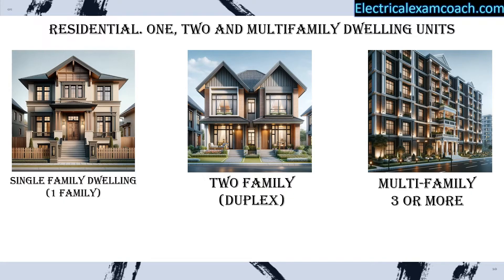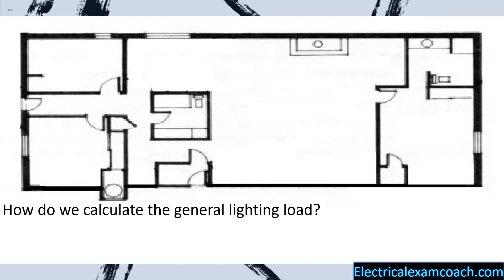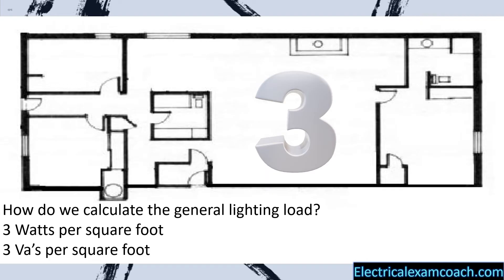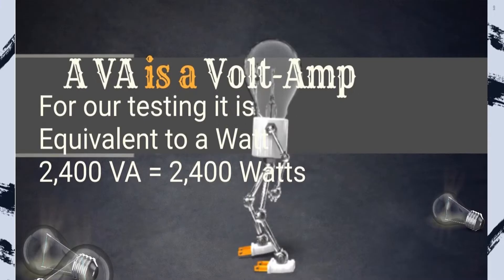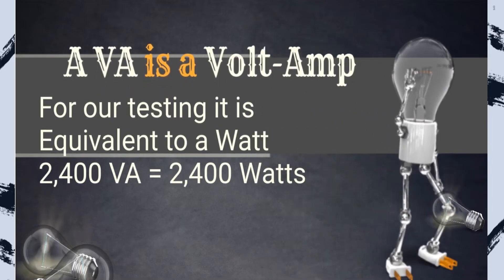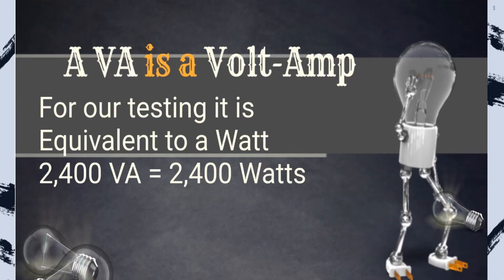The first question we have to ask is how do we calculate the general lighting load? Are we going to calculate it per receptacle outlet, per lighting fixture — do we have to count them all up? Thankfully, no — they've made it very simple. We're going to calculate it at three watts per square foot. So for all of the general lighting and all of the general receptacles, all we have to do is take the square footage of the dwelling unit and multiply it by three. The code language actually uses VAs — volt amps — so three VAs per square foot. For our testing, a VA is equivalent to a watt, so 2,400 VAs equals 2,400 watts.